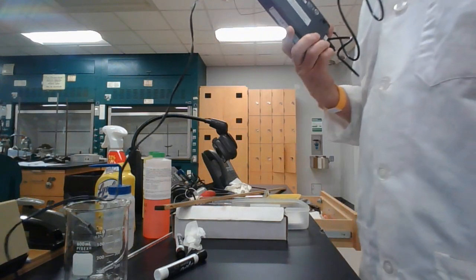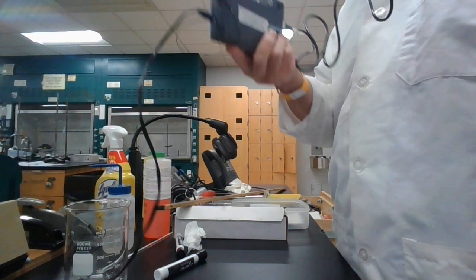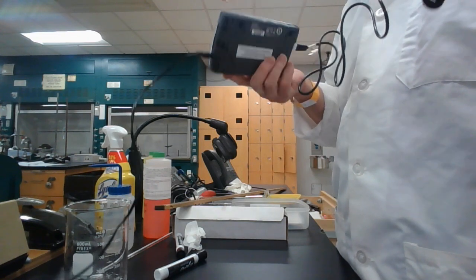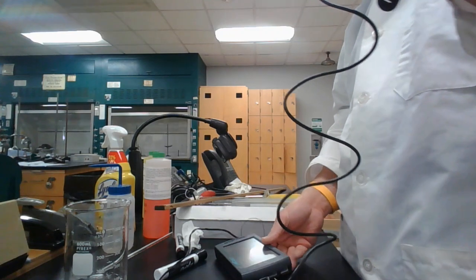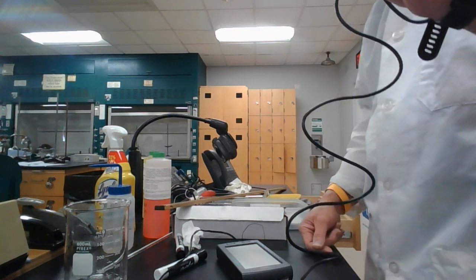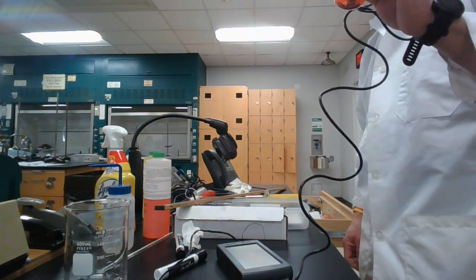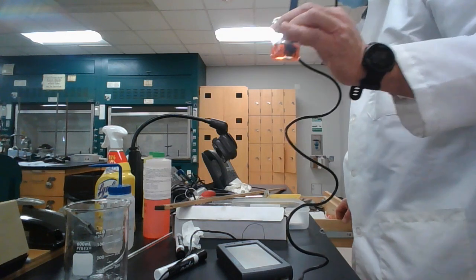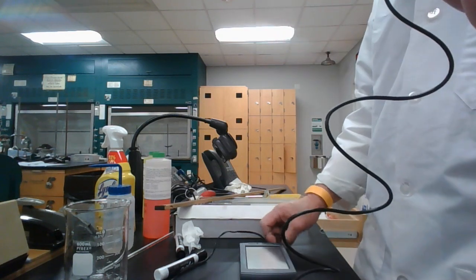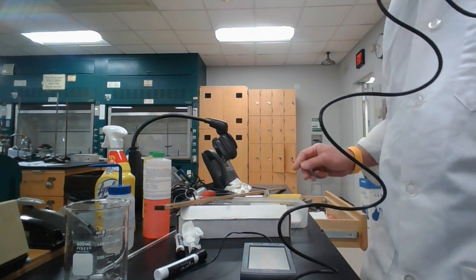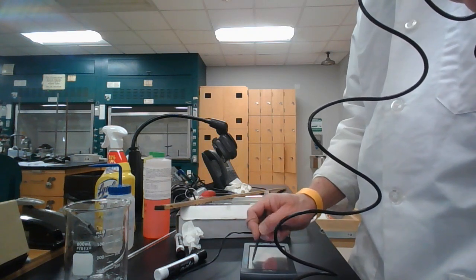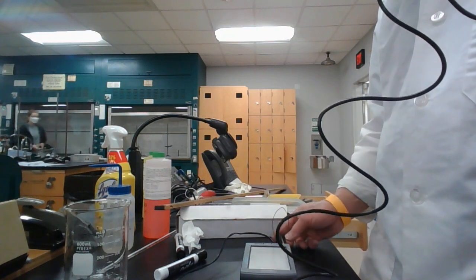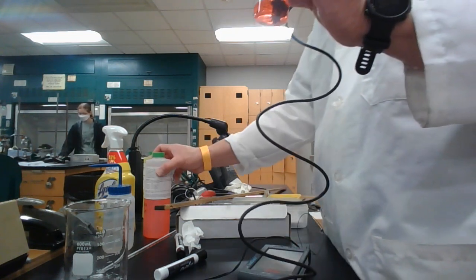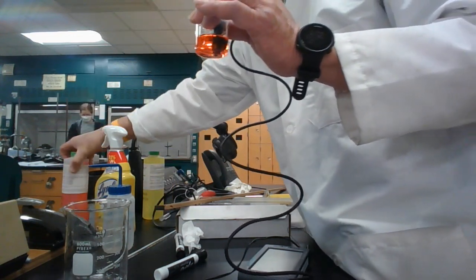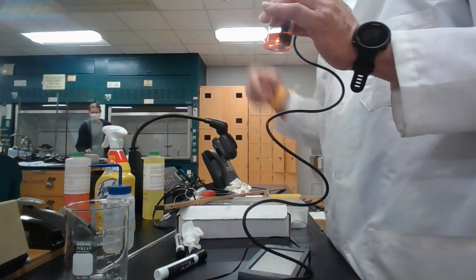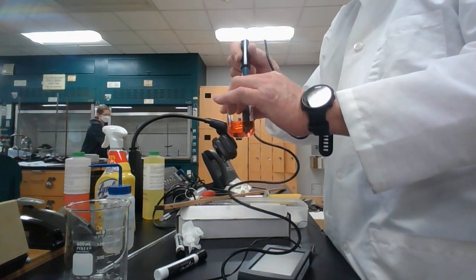Okay. Let's say it wasn't reading 4.00. Let's say yours was way off calibration. If yours was way off calibration, this is what we do. Mine might not need any calibration. Okay, what we do is this. There's a little stylus here that you can use, and we'll go to sensors. But while we do this, why don't you come and get a little bit of the pH 4 buffer into your little plastic beaker, enough to cover this.